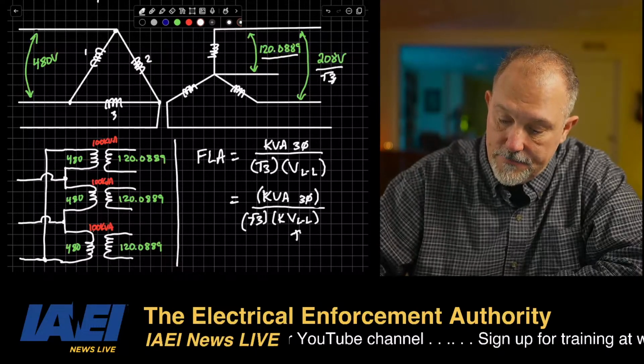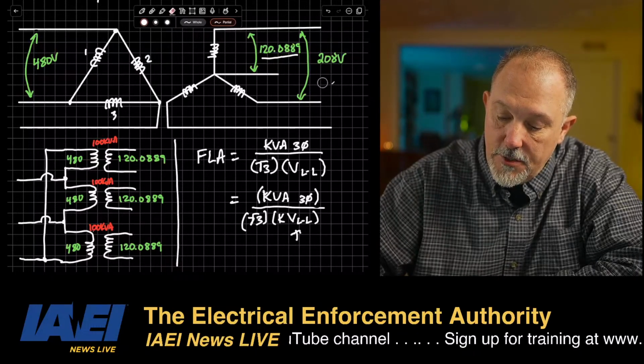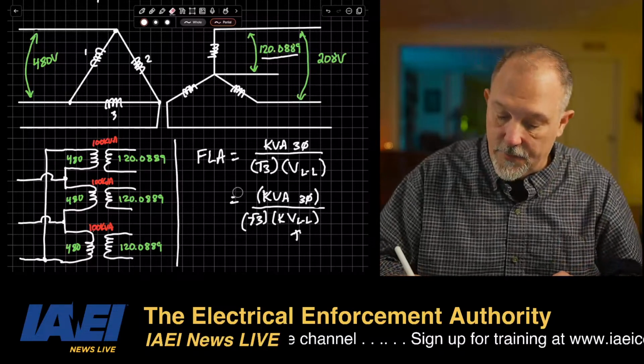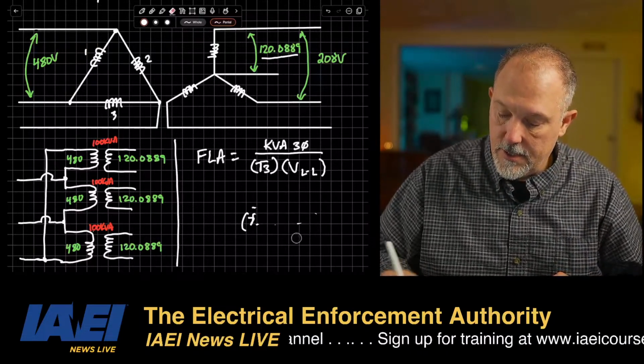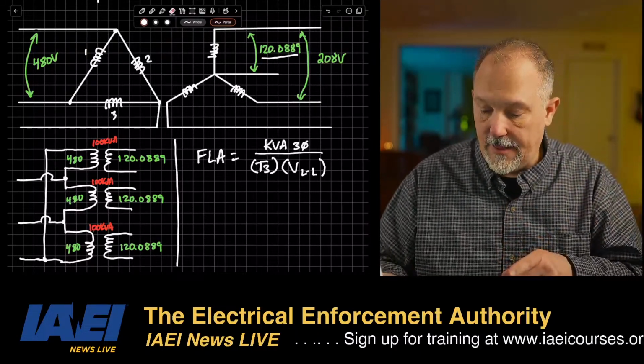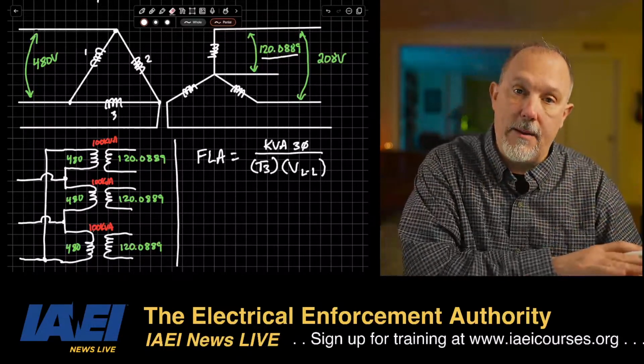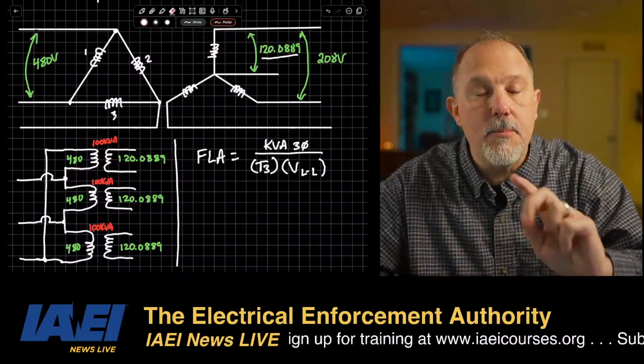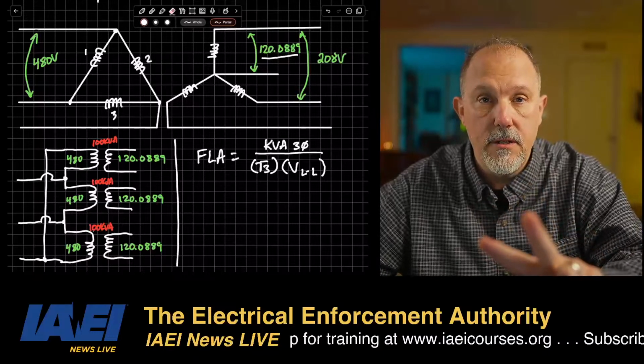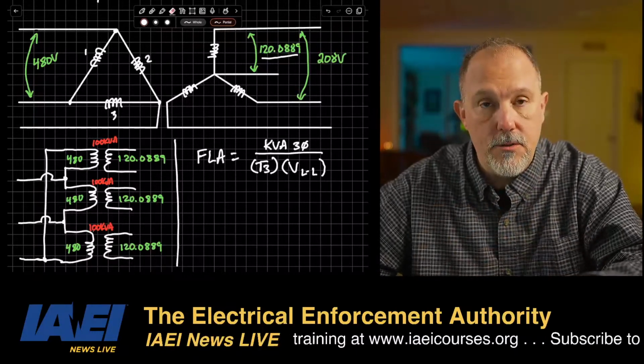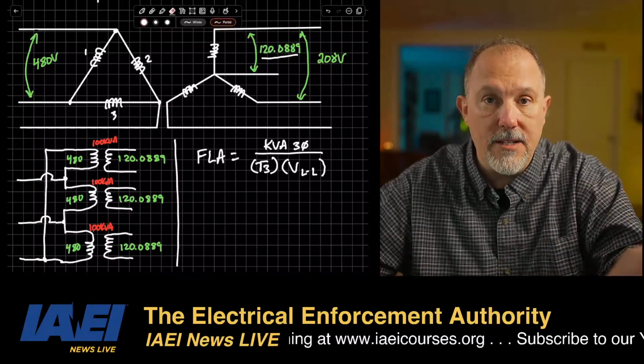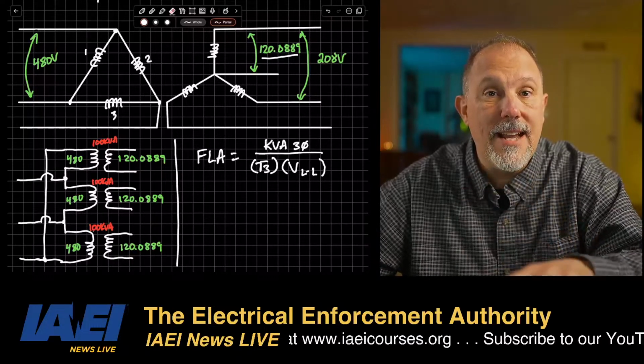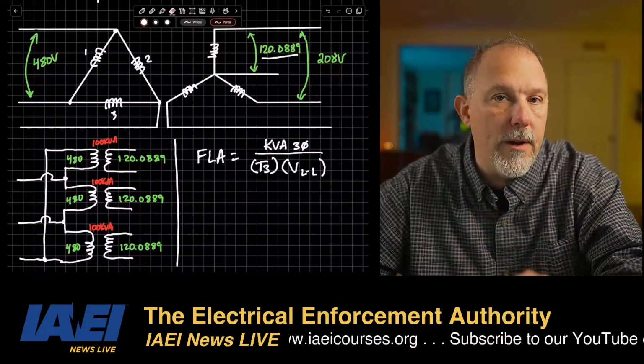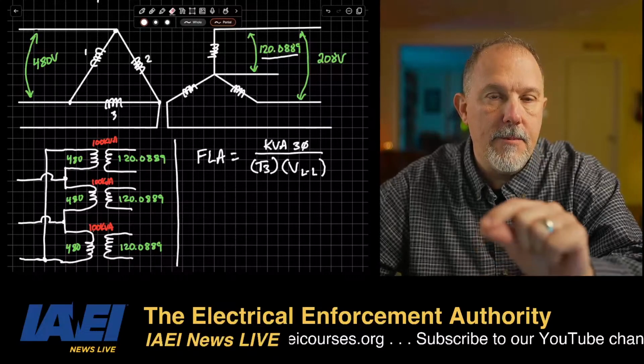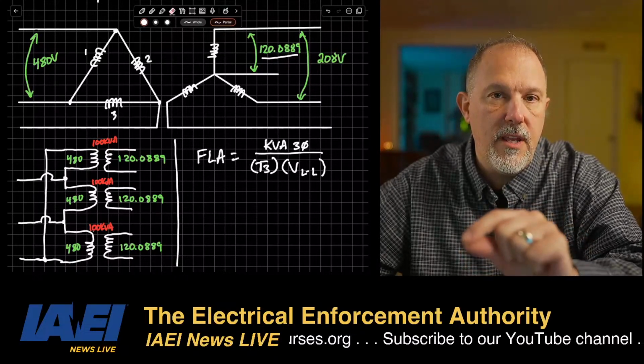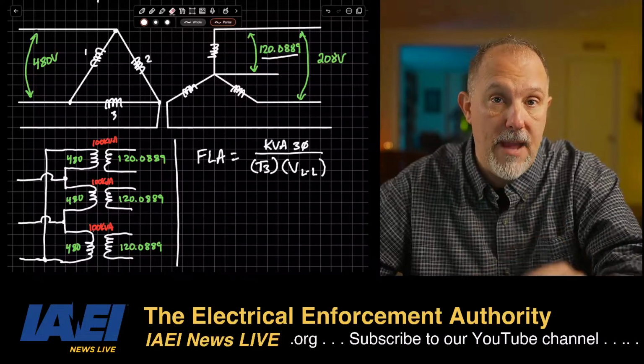So now, what I want to do is I'm going to calculate the full load amps on the secondary, and then we're going to reflect it to the primary. And we're going to reflect it to the primary using 2 methods. One, the method I always use, 480 over 208 as my turns. And the second, we're going to use 480 over 120. And I'm going to show you what you need to do if you're going to do that math.